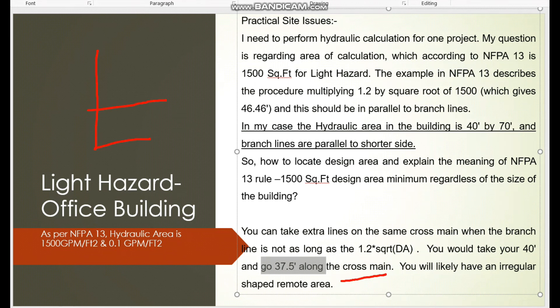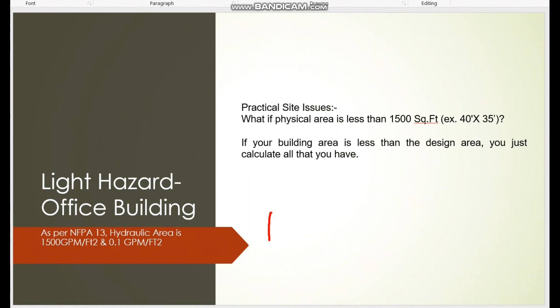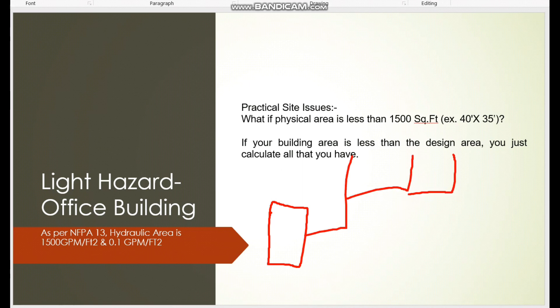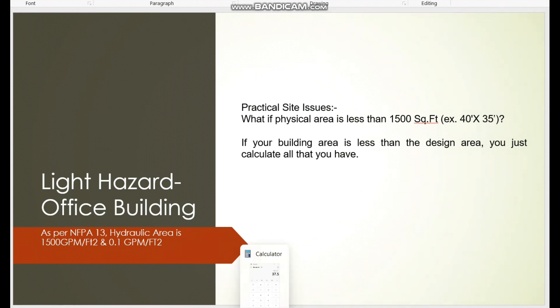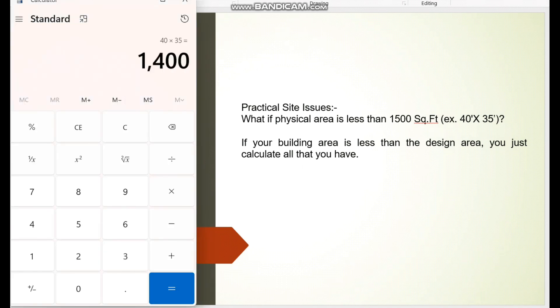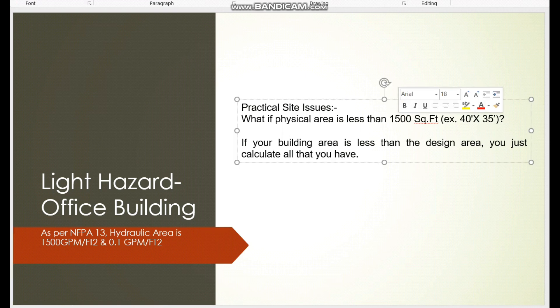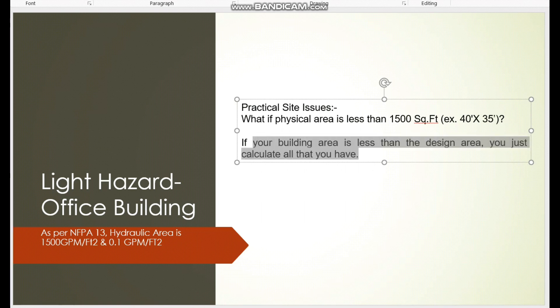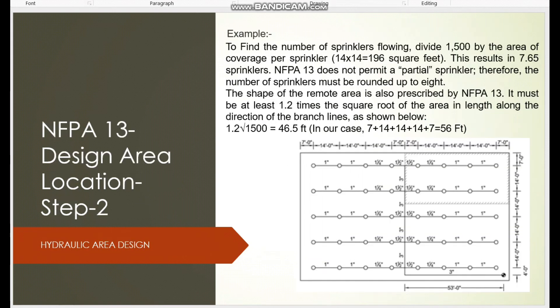The important condition is that you must consider sprinklers from the same cross main — you should not move to a different cross main for the hydraulic area. Another question: if your pump supplies multiple buildings and the remotest building is 40 feet by 35 feet = 1400 square feet, which is less than the required 1500 square feet per NFPA 13 — the answer is: if the building's hydraulic area is less than the design area, simply calculate with whatever area you have.